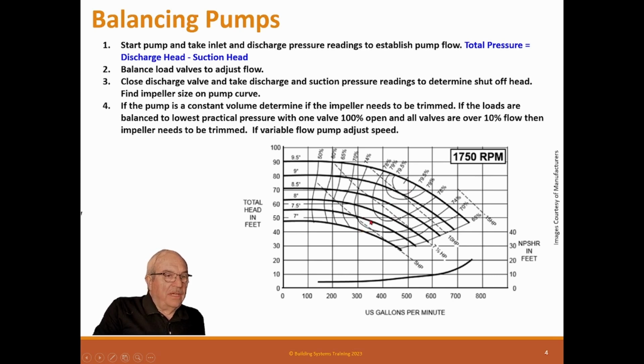And if you do that, you risk the chance of someone coming on and working the pump, if you've got that discharge valve balanced down, and they open that valve full, or they close it down to work on the pump, and then they open it full because they don't know where it was. And then you could actually maybe go into overamp. So, I mean, it's a bad idea to use that valve as a balance valve. It's better to trim the impeller or to balance the load down in the field.